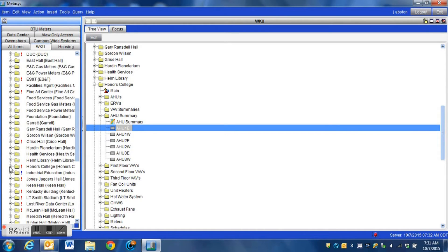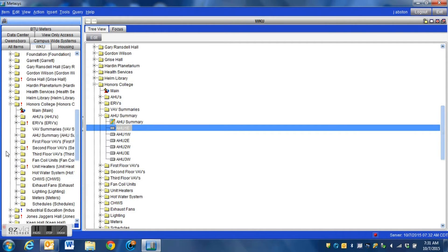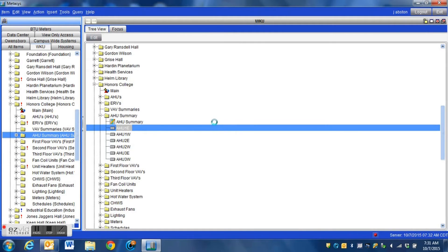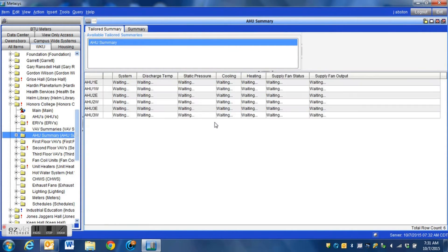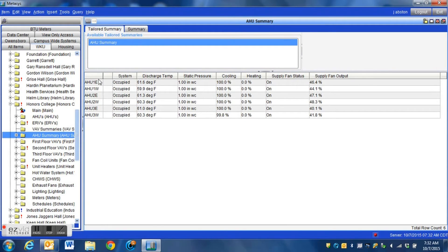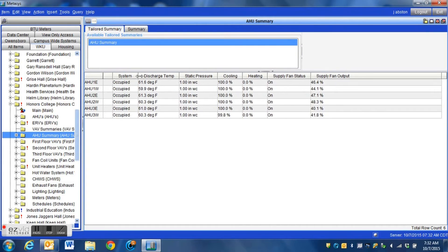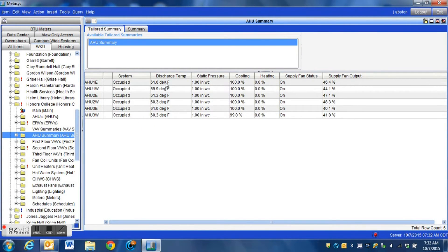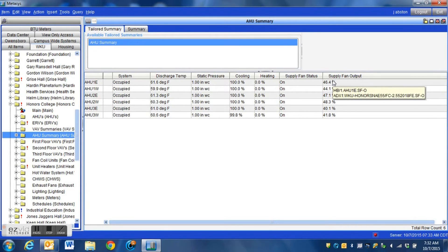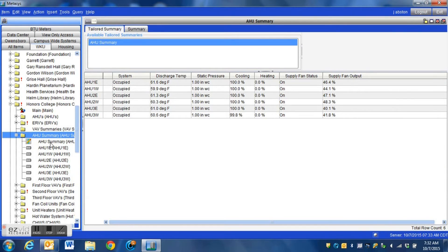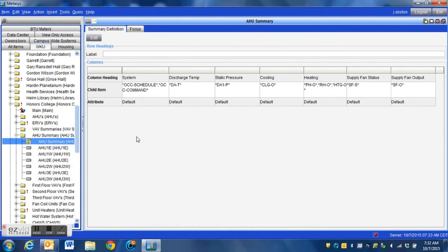Now let's go down and have a look at what our summary definition does for us. Here is the folder right here where we have created the summary definition. We're going to pull that whole folder over into our display - it may take a minute to populate depending on how many controllers you're pulling in. But here we are - we can see over in the far left we have the particular air handler name, we have the current state of the system whether it's occupied or unoccupied, we're looking at the discharge temp, static pressure, we can tell what our cooling and heating valves are doing, we can see that the fans are running, and what the VFDs are running at percentage-wise. So this is a very very powerful tool that can really help speed up the process of checking over your buildings.